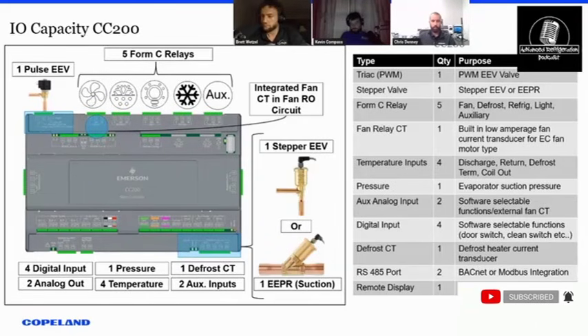Okay, so moving on the bottom here, the temp inputs, we got one input for defrost CT, which is exactly what Kevin was talking about. We sell a CT that's 4 to 20 milliamp to get maximum accuracy. You just wire it off this plus 12 volt power tap and then over into the defrost CT input. We have two auxiliary inputs as well. Those can be satellite for E3 or do some other functions as well. I forgot to mention the RS-485 ports up here. So this is where we're going to do BACnet Modbus. And then coming very soon, when A2L support rolls out, we will have an A2L refrigerant sensor communication tapping off here.